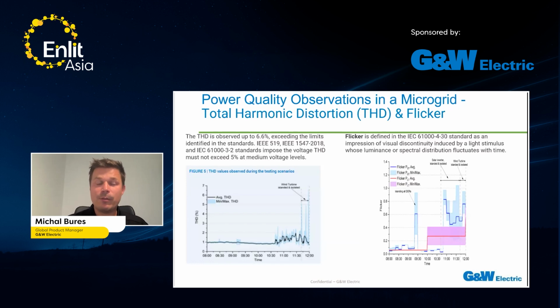It's not everything. We also measured THD and flicker. Total harmonic distortion was observed at the level of 6.6%, so it is exceeding the limit given by the IEEE standard, which allows a maximum of 5%. So we were above this value, and of course, you can see on the right side that flicker was observed too. You can see again the timeline. So this phenomenon was again related to the DERs' manipulation.